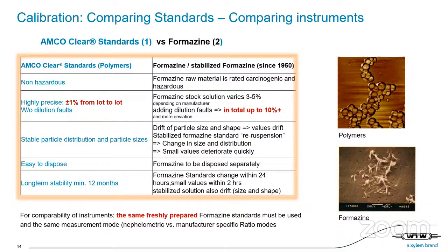And if you look at the US EPA or also DIN ISO regulations, you will see that usually 10% is already stated in the standard method regulations as occurring. And then if we have, for example, formazin and let it stand for a while, if it's a higher concentration it's not as bad, but in a small one, it settles. So you have to shake and swivel the glass. And then if you do that, it's falling apart like the chewing gum. This is called deterioration. So it will fall apart. And finally, formazin standards which are freshly prepared, at small values, are only stable for 2 hours. Today, there are stabilized solutions, but if you haven't opened them freshly, they will deteriorate.